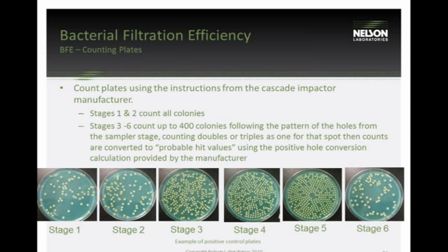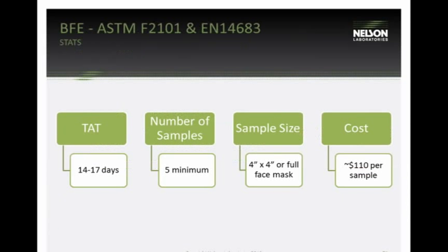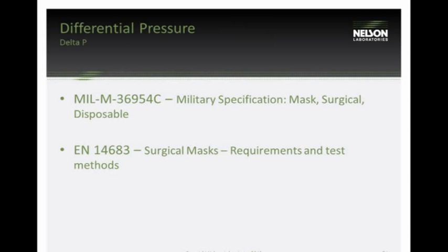After testing, the Andersen sampler plates are incubated for 2 days at 37°C — results cannot be seen until at least 2 days after the test runs. The BFE test has about a 14-to-17-day turnaround time. Minimum number of samples is 5, with a sample size of about 4 inches by 4 inches or a full face mask. Cost is approximately $110 per sample. A statistically valid number of samples must be tested to support product claims.